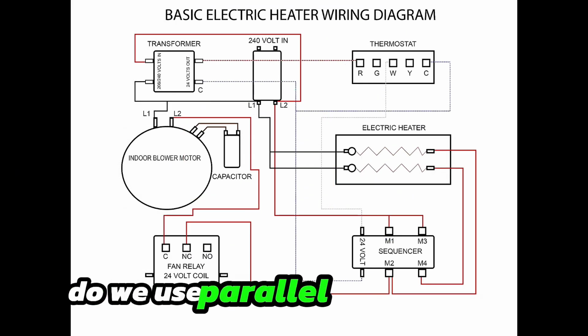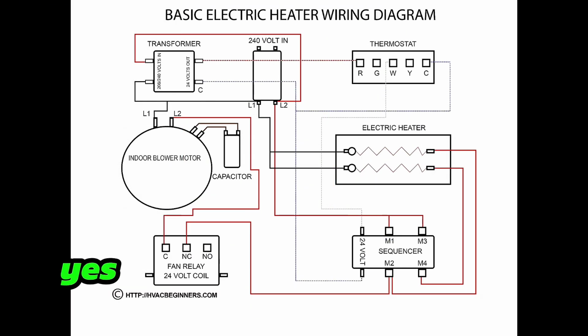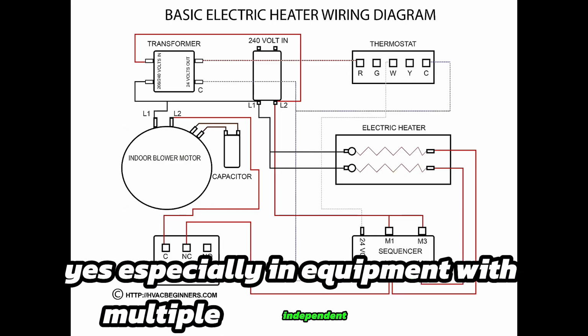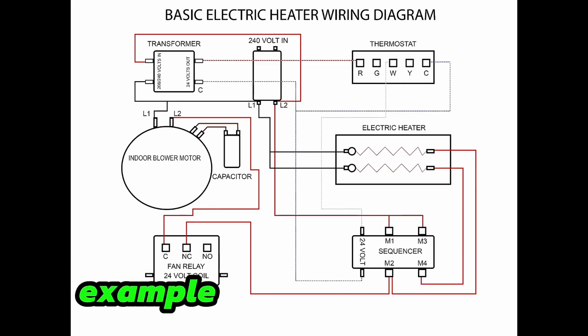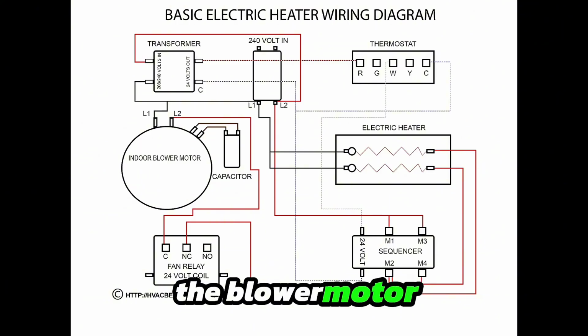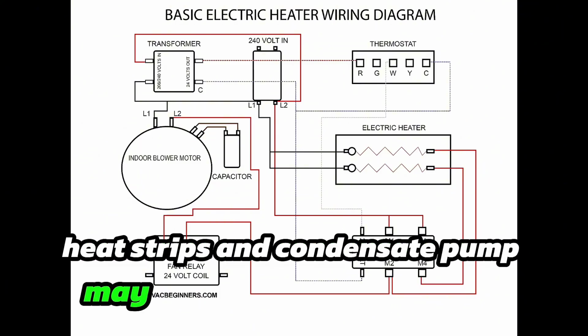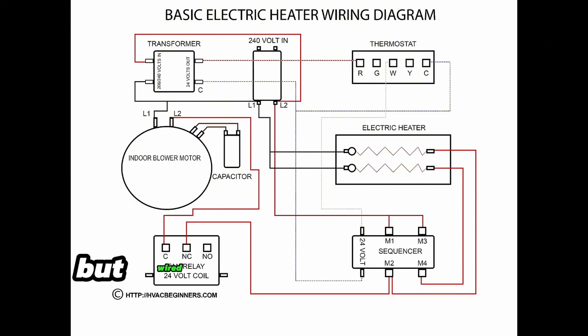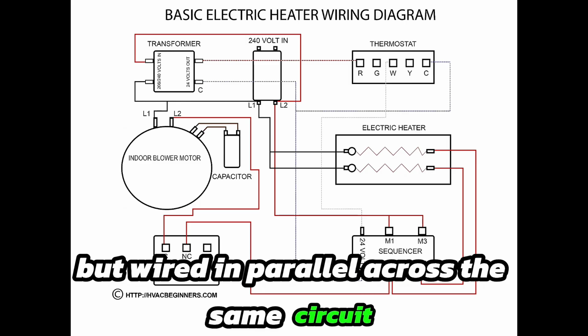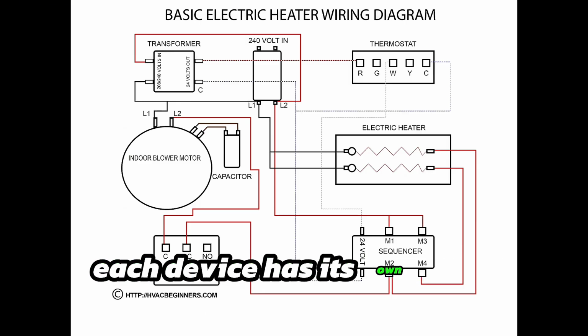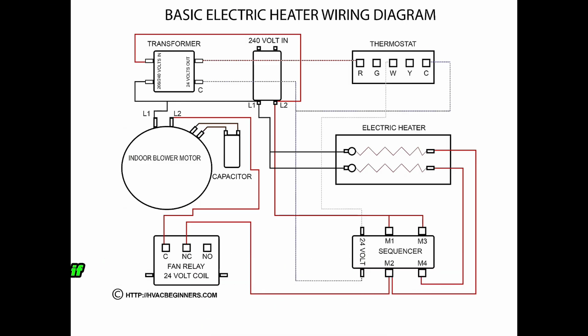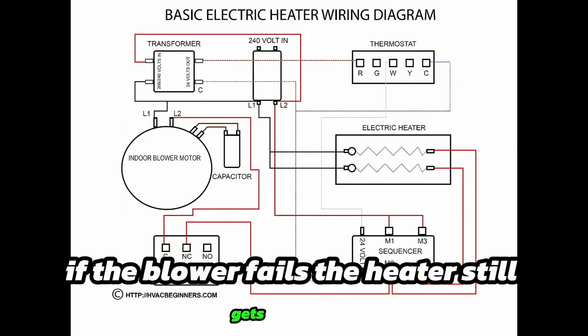Do we use parallel with 240 volts? Yes, especially in equipment with multiple independent loads. Example, inside an air handler, the blower motor, heat strips, and condensate pump may all be powered by 240 volts, but wired in parallel across the same circuit. Each device has its own path from L1 to L2. If the blower fails, the heater still gets power.